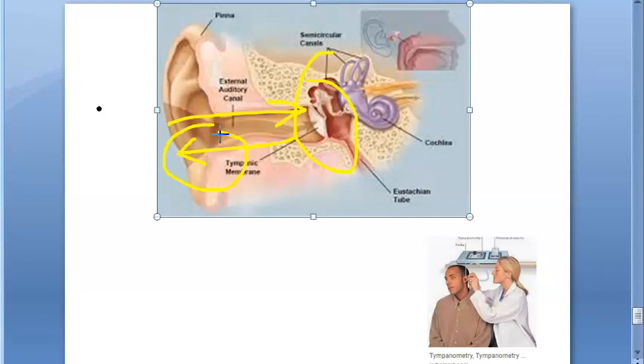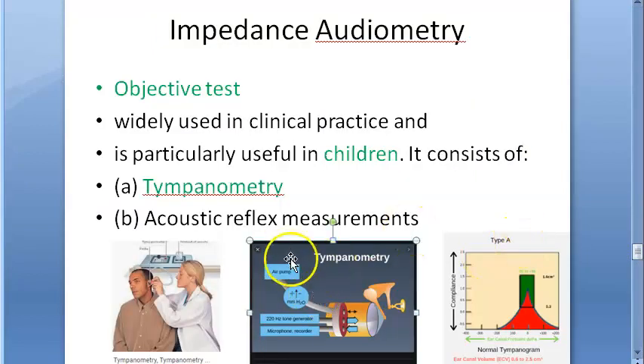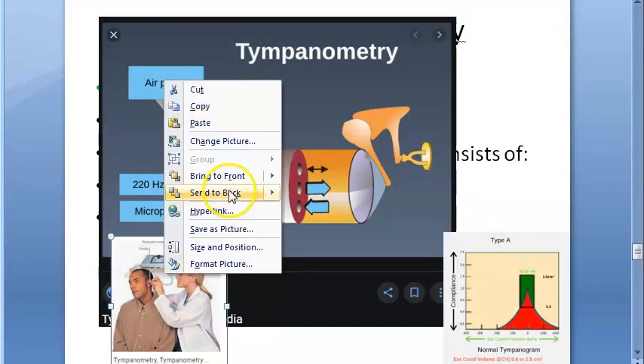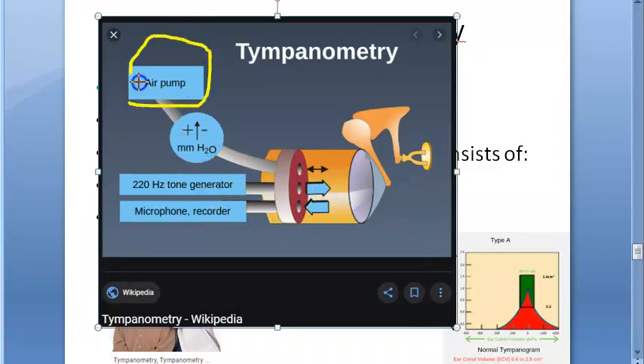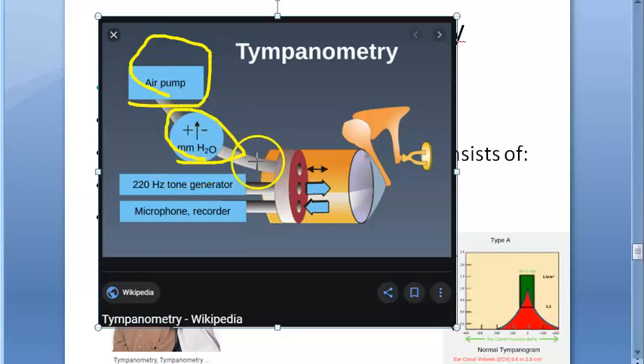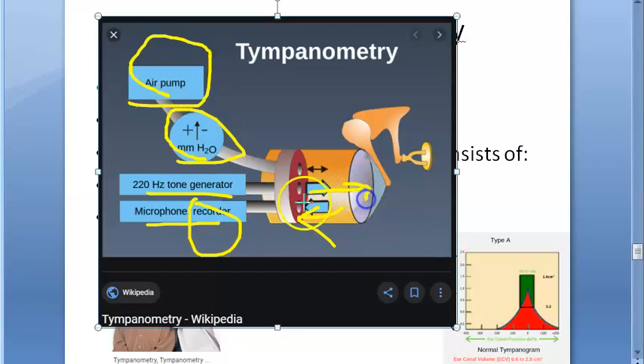What will happen if the tympanic membrane has become stiff? It will reflect more of the sound. Now looking at the setup: in tympanometry there are three things — an air pump maintaining pressure in millimeters of water, a frequency generator, and a microphone which records the reflected sound energy. This is the input from the tone generator.